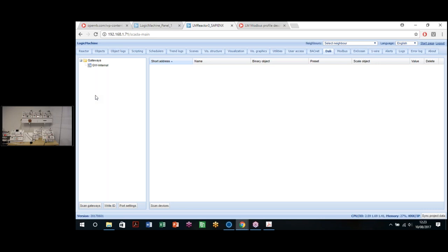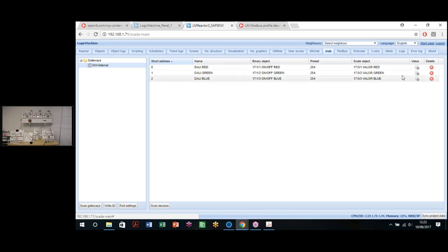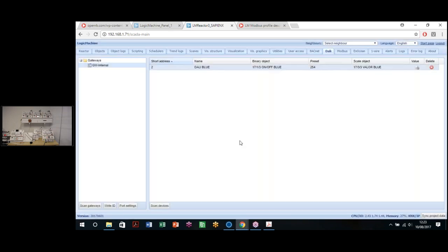RS-485 gateways installed in our logic machine, extension gateways, it will show in here once we click on scan gateways. This will scan the internal gateways and the external connected gateways also. So to look for the different ballasts that we have installed in our DALI, I have already created. Let's erase all of this. Erase. Okay. So to find the ballast that we have connected, we install all our installation or our DALI installation.